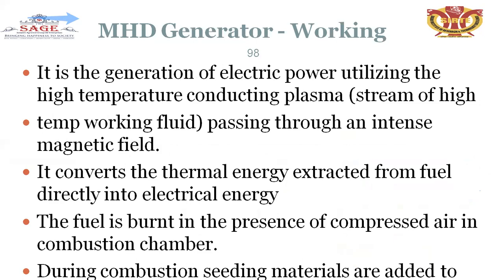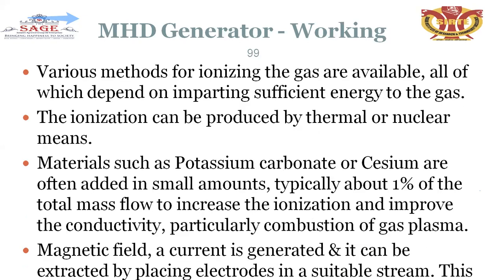The MHD generator works by generating electrical power utilizing high-temperature conducting plasma. A stream of high-temperature working fluid passes through an intense magnetic field, converting thermal energy directly into electrical energy. Fuel is burned in the combustion chamber in the presence of a compressor. During combustion, seeding materials are added; various methods for ionizing the gas depend on imparting sufficient energy. Ionization can be produced by thermal or nuclear means. Materials such as potassium carbonate or cesium are added in small amounts (typically about 1% of total mass flow) to increase ionization and improve conductivity of the plasma.